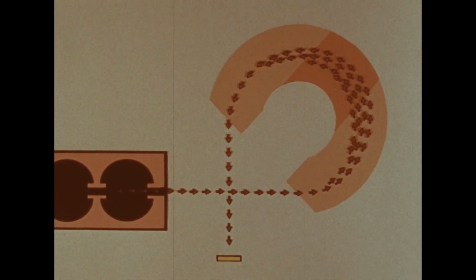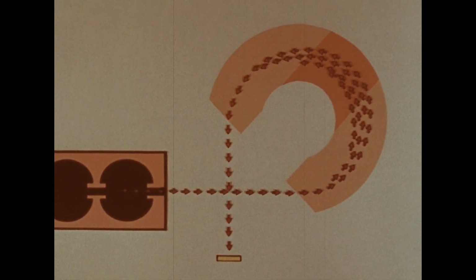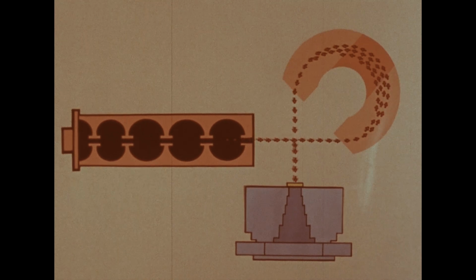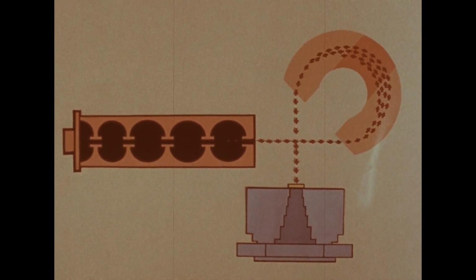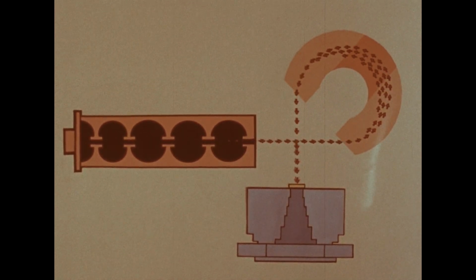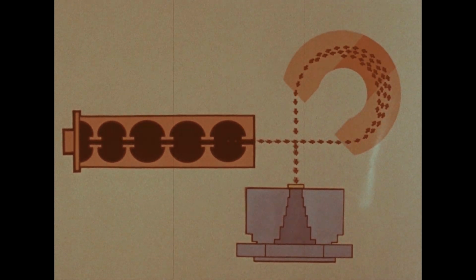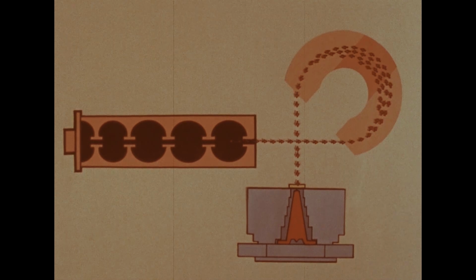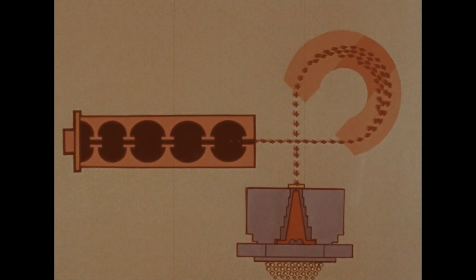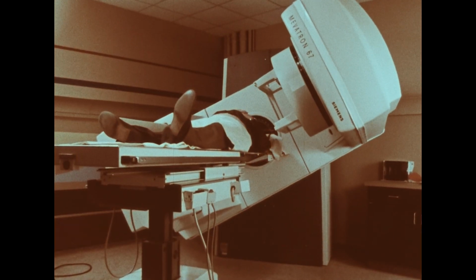The target is a thin gold layer with an absorber, which is necessary to get a clean photon beam. Next, the therapeutic useful beam is defined by a stepped primary collimator which reduces scattered radiation, then passes through a specially designed flattening filter. The result is a perfect photon beam of very narrow energy, flattened with minimal electron contamination, ideally suited to high-energy cancer radiation treatment.